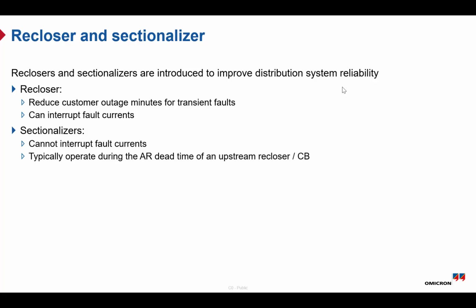Now let's look at a recloser and a sectionalizer, how they work together and what the key differences are. Both devices are used to improve the reliability of the distribution system. Starting with the recloser, its main role is to reduce the outage time, especially for temporary faults. For example, if there is a transient fault like a lightning strike, the recloser can trip and then automatically close again. So if the fault is gone, the service is restored quickly. Also, a recloser can interrupt a fault current as it's a circuit breaker.